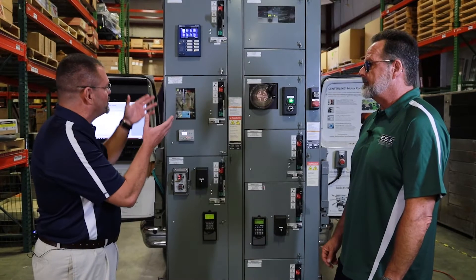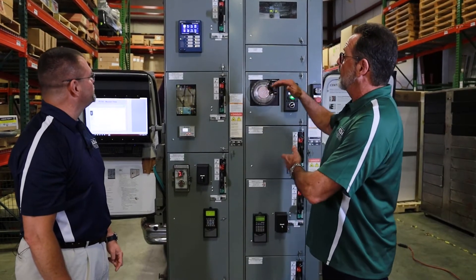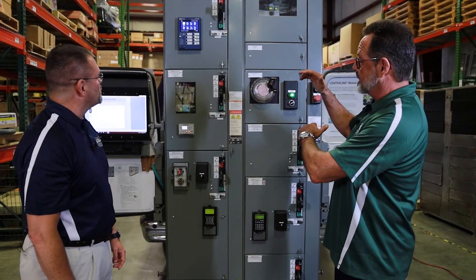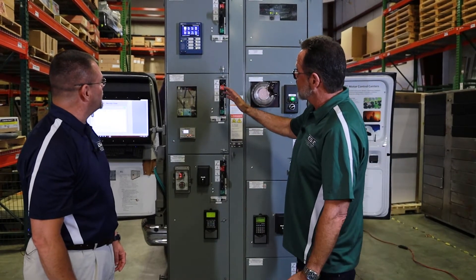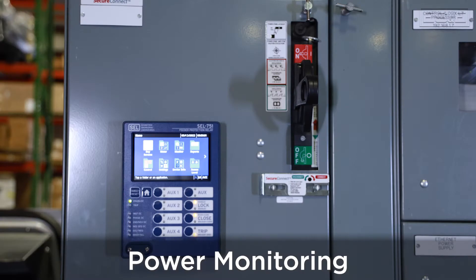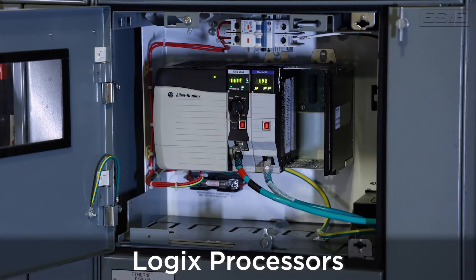We're standing next to the MCC — we've got a lot of options and a lot of buckets, so what are my options? Mark, MCCs are highly configurable with different size buckets — vertical sections comprised of one space factor up to six space factor sections. Each one of these sections can house a motor control starter, power monitoring, a VFD, ethernet supply, and ControlLogix processors.